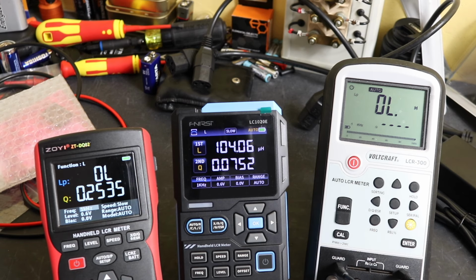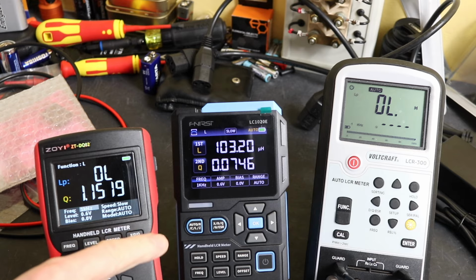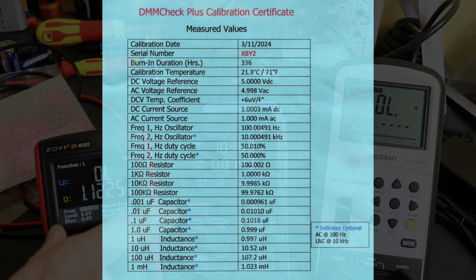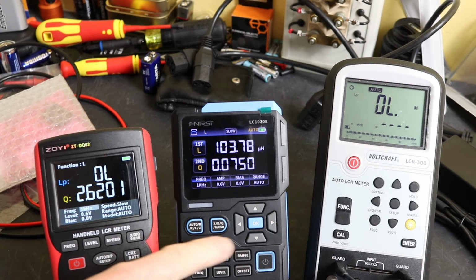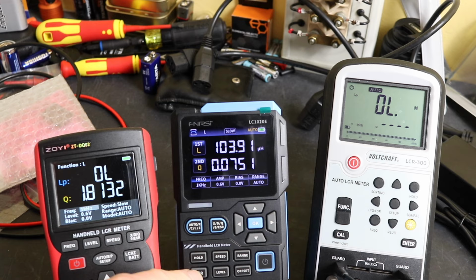Another one was the frequency that we are using. So I thought at the time, I seem to remember that the certificate for the DMMCheck Plus was 1 kHz. It wasn't. It's actually 10 kHz. I'm using 1 kHz because that's what I use for all the motors that I test. But we can change the frequency up. There's our 10 kHz reading there, which should match the certificate. And we are 103.7165. So not much of a difference really.